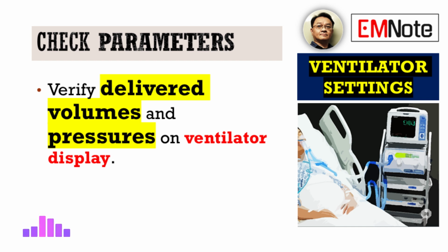So first things first, how do we verify what the ventilator is actually delivering compared to what we've programmed it to do? Can we trust the machine's readouts? Generally, yes, but you must regularly check the delivered volumes and pressures displayed right there on the ventilator screen. Think of it as ongoing quality control. It ensures the machine is consistently performing as programmed and delivering the intended support to the patient. It serves as a double check against any subtle discrepancies or potential malfunctions within the ventilator's internal system. Those displays should ideally match your prescribed settings, or at least show acceptable variance based on the patient's lung mechanics.